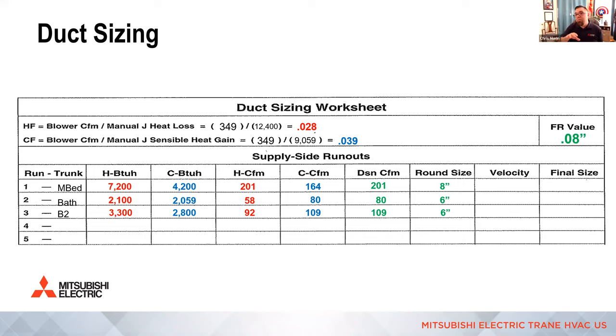So the rule of thumb, or the mins and maxes, don't change for design when it comes to velocity. What changes is the volume of air that you're going to be needing, because the system's going to be smaller, all right? And what ends up happening is the lower the volume of air and the lower the static pressure, the more obvious duct design issues become, because you don't have the pressure or the volume of air to overcome that, right? So these still apply. The lower the static, the more obvious and the more detrimental a mistake becomes.